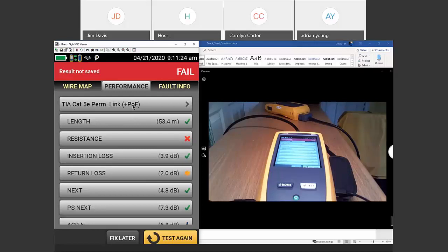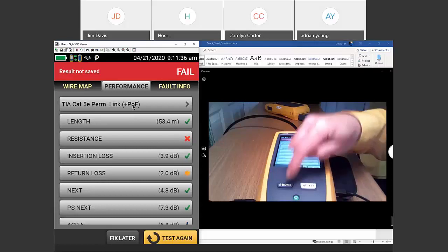Yeah, actually, I was just typing the answer to it. How concerned should I be when my contractor submits test results with a generic cable type, i.e. 6A, as opposed to specific manufacturer's cable where the values such as NVP can vary?